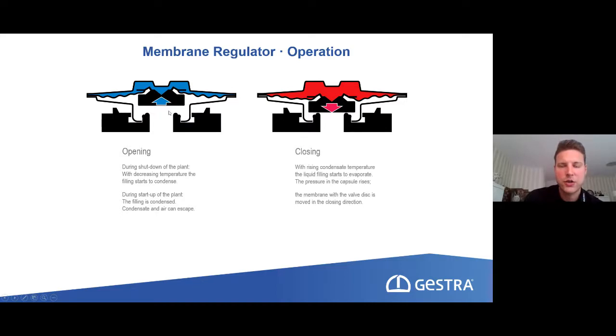It's not much. It's only 10 Kelvin roundabout, and then after a while, this vapor we have here, the steam alcohol mixture, will start to condense. So we are then losing the pressure here, and then we will have the membrane which will pull, let's say, the plug from the seat, and then we can go ahead with the working, because then we will discharge the condensate. So this is very much how it works.